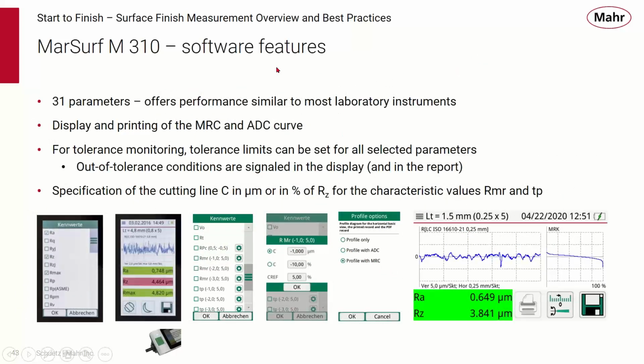Here are some of the important software features for the M310. Again, 31 parameters, very similar performance to most laboratory surface finish measuring systems. We have display and printing of the MRC and ADC curves. For tolerance monitoring, tolerance limits can be set for all selected parameters, and out-of-tolerance conditions are signaled on the display and on the report, so you can see color coding for things that are in or out of tolerance. And you can have specification of the cutting line C in micro inches or percentage, which makes it easier to understand your MRC curves.